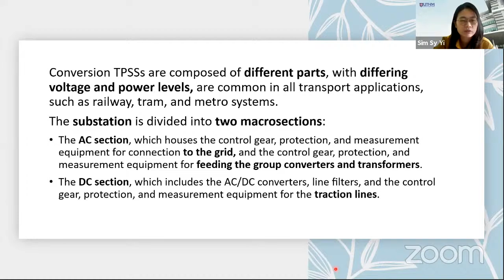So the upper part here is our HVAC, and the lower part is our DC part. For the AC, coming from the primary lines, we have the three-phase disconnector. The circuit breaker serves the same function, to open the circuit when there is a fault, but the difference is the disconnector cannot be opened when there is a load. These two things provide redundancy for double safety purposes, so if one fails, we still have another for safety.